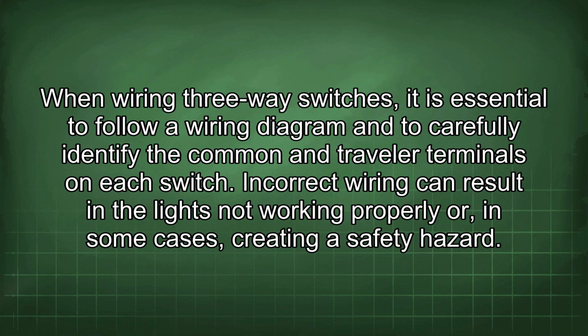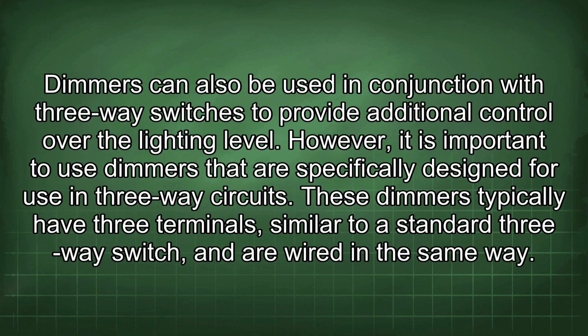When wiring 3-way switches, it is essential to follow a wiring diagram and to carefully identify the common and traveler terminals on each switch. Incorrect wiring can result in the lights not working properly or, in some cases, creating a safety hazard. Dimmers can also be used in conjunction with 3-way switches to provide additional control over the lighting level.